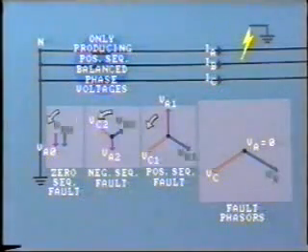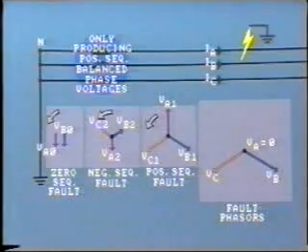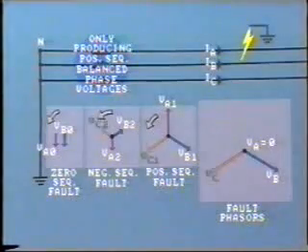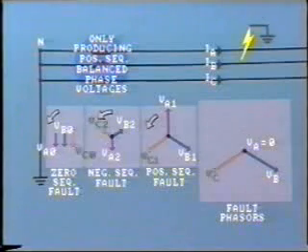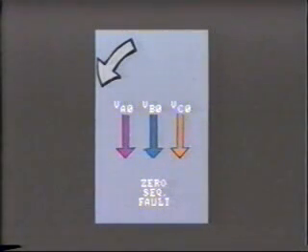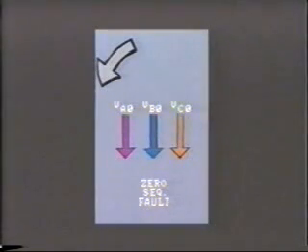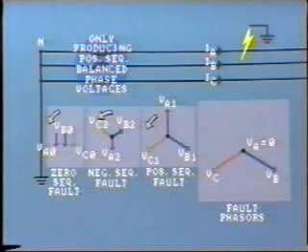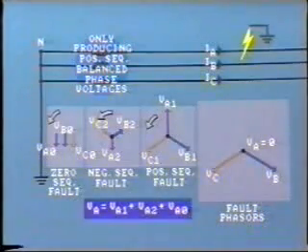Now let's look at the B phase components. We know that the phase voltage VB remains unchanged. Thus, the fault voltage VB is the sum of VB1, VB2, and the missing component VB0. Check in your workbook to verify that these phasors add to give VB. Similarly, with the C phase voltages, the phase voltage VC at the fault is obtained by adding VC1, VC2, and the missing component VC0. Another interesting factor becomes apparent: the zero-sequence components in each of the phases are of identical magnitude and all are at the same phase angle. In fact, these voltage components have no sequence at all, so they are called zero-sequence components. To review, to get each phase voltage at the fault, we add the three components together — for example, VA equals VA1 plus VA2 plus VA0.